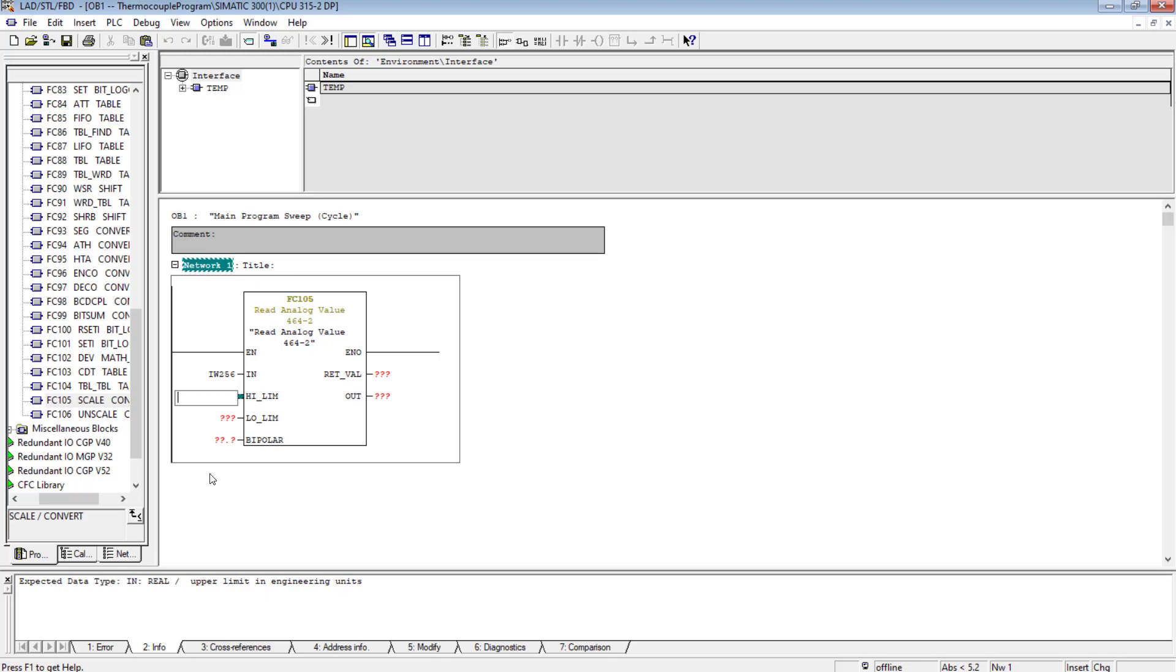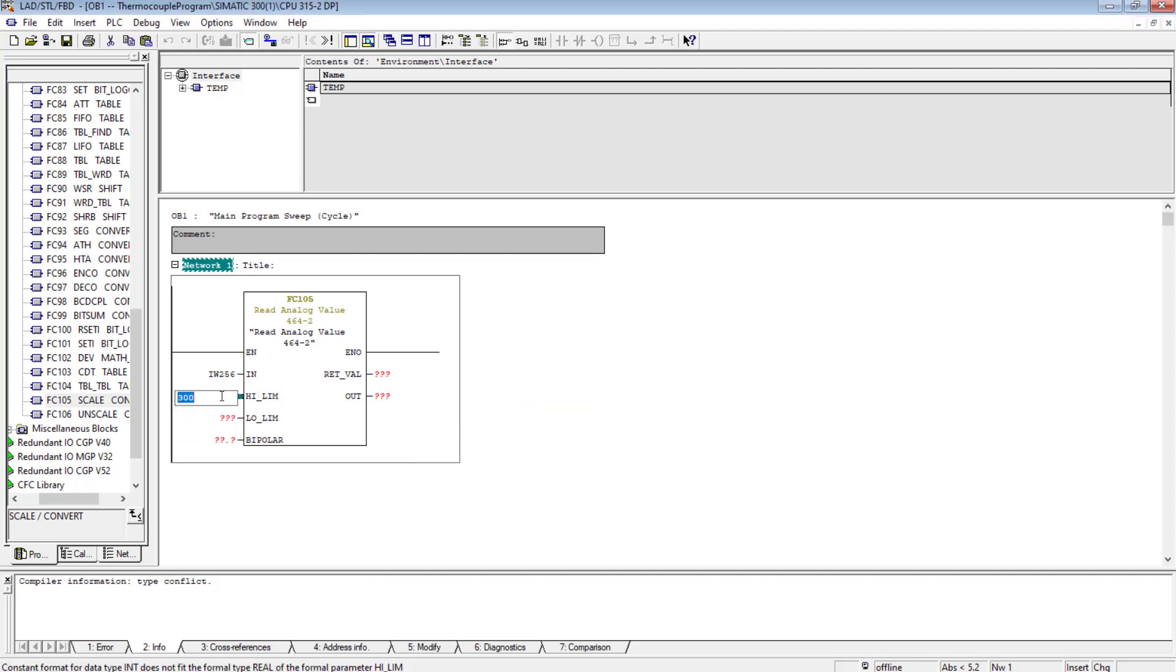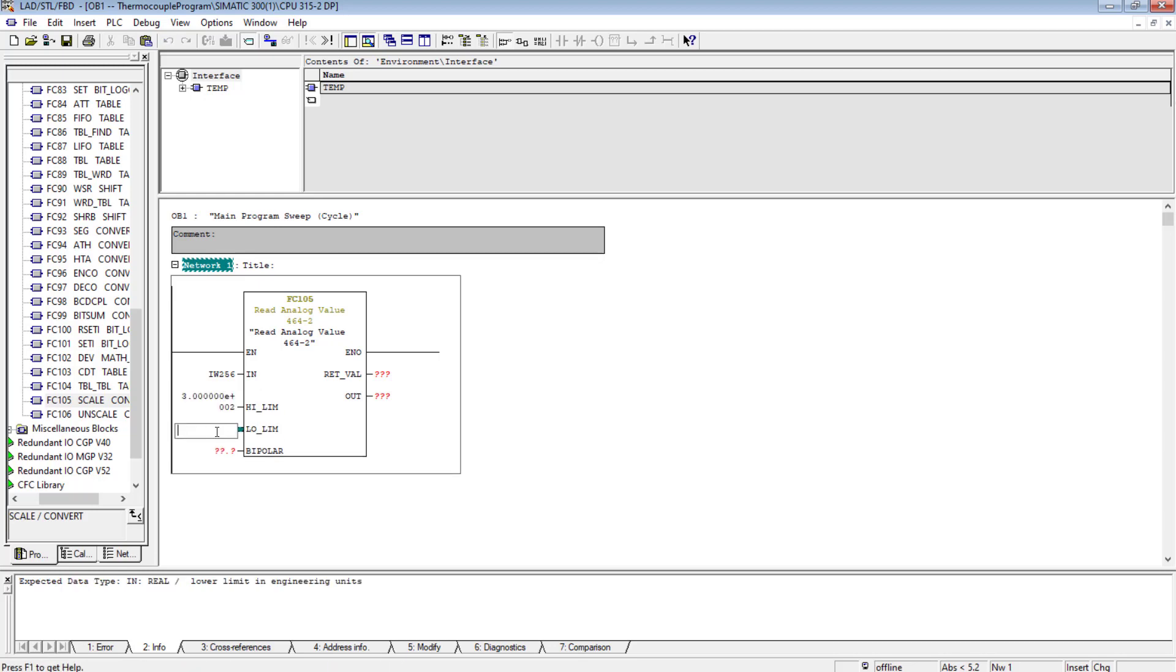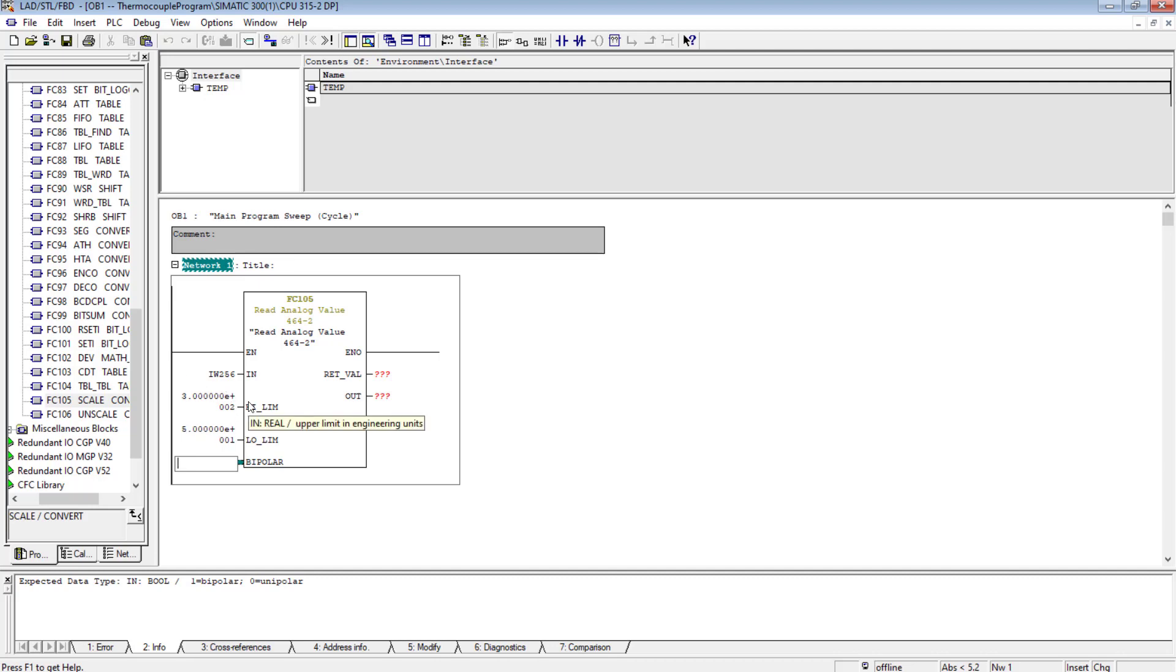IW 256. Now remember whenever we interface any sensor, be it temperature sensor or any other analog sensor, the scaling of the sensor must be accomplished. The minimum measuring value of the sensor and the maximum measuring value of the sensor - every sensor, the nameplate or the datasheet or the manual has information about in which range this sensor is going to make measurements. For example, this is a 0 to 250 degrees centigrade thermocouple, or for example 50 to 300 degrees centigrade thermocouple. So the higher value in this case is 300 degrees centigrade and 50.0. In this case, 50 is the minimum measuring value of this thermocouple and 300 is the maximum measuring value. This is the high and low limit, the low scale and high scale, the measurement scale of the temperature sensor.